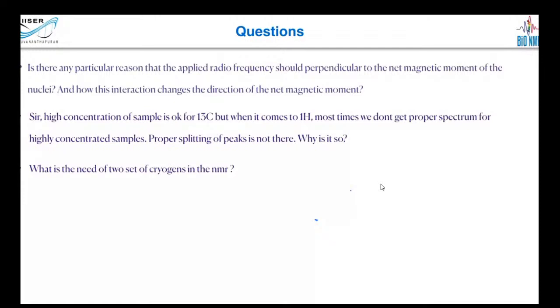The heat has to be transmitted from the sun to earth, right? And in between it is space, and still heat transfers. In the same way, even if there is vacuum, heat will transfer from outside into the helium vessel at helium temperature. That will warm up the helium and we will quench the magnet.